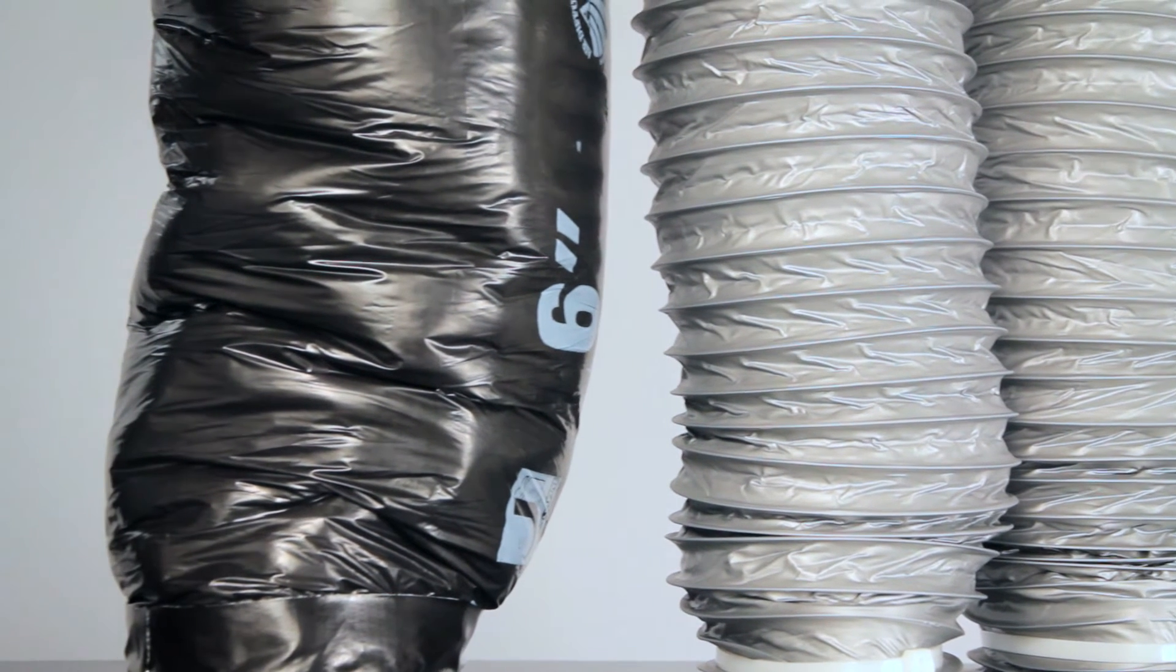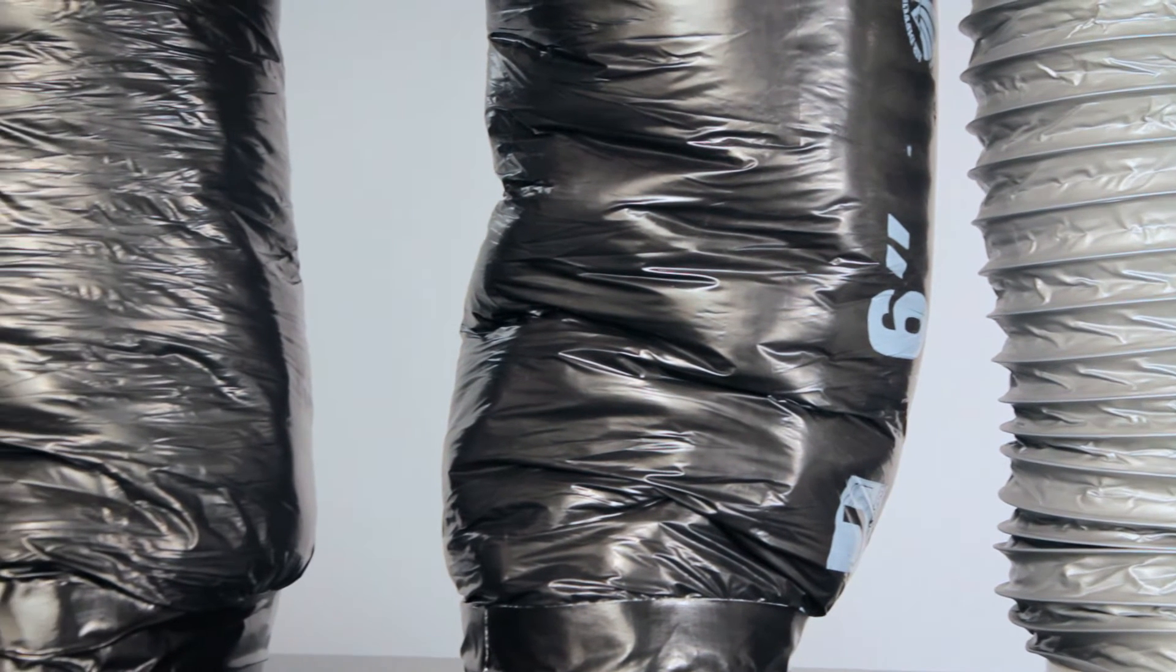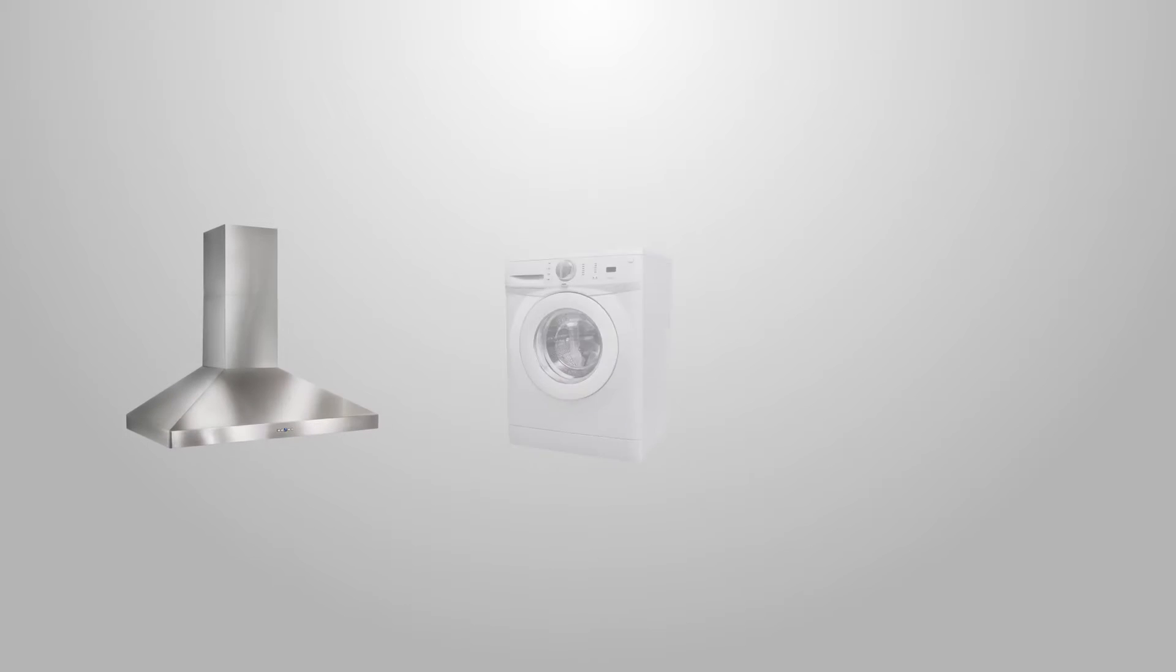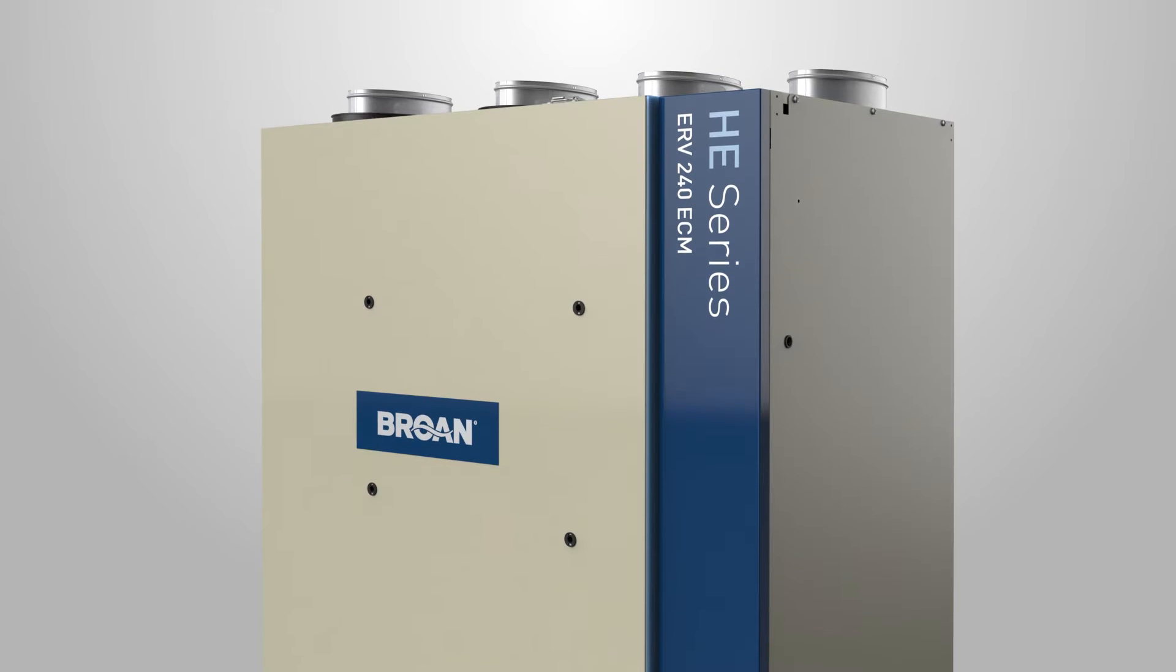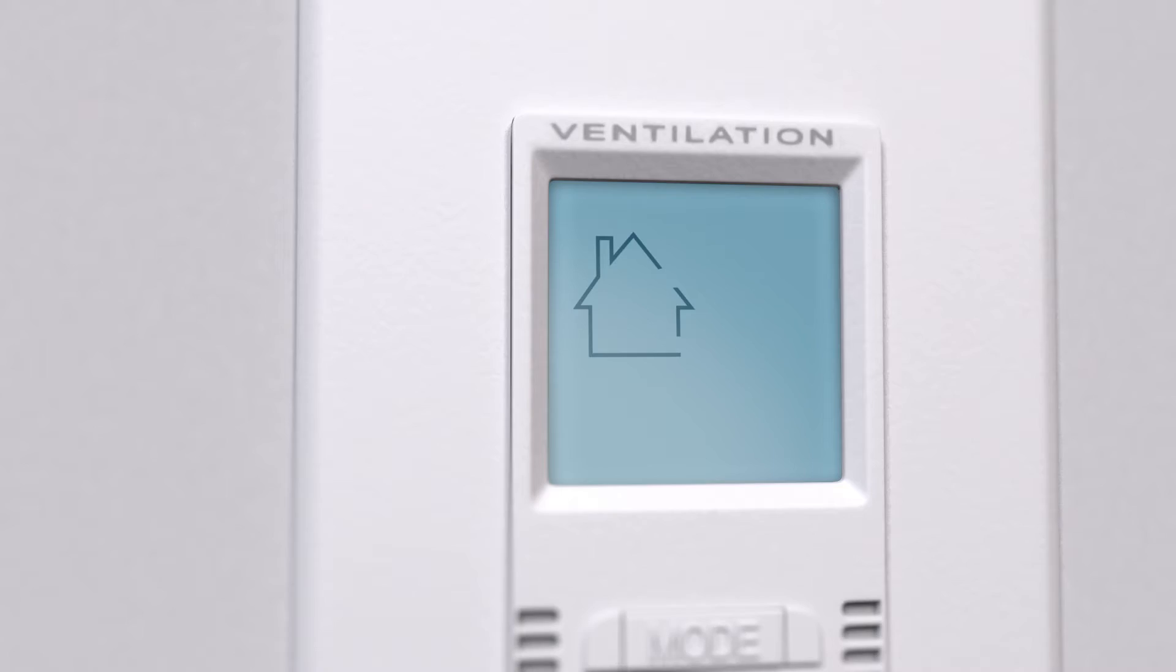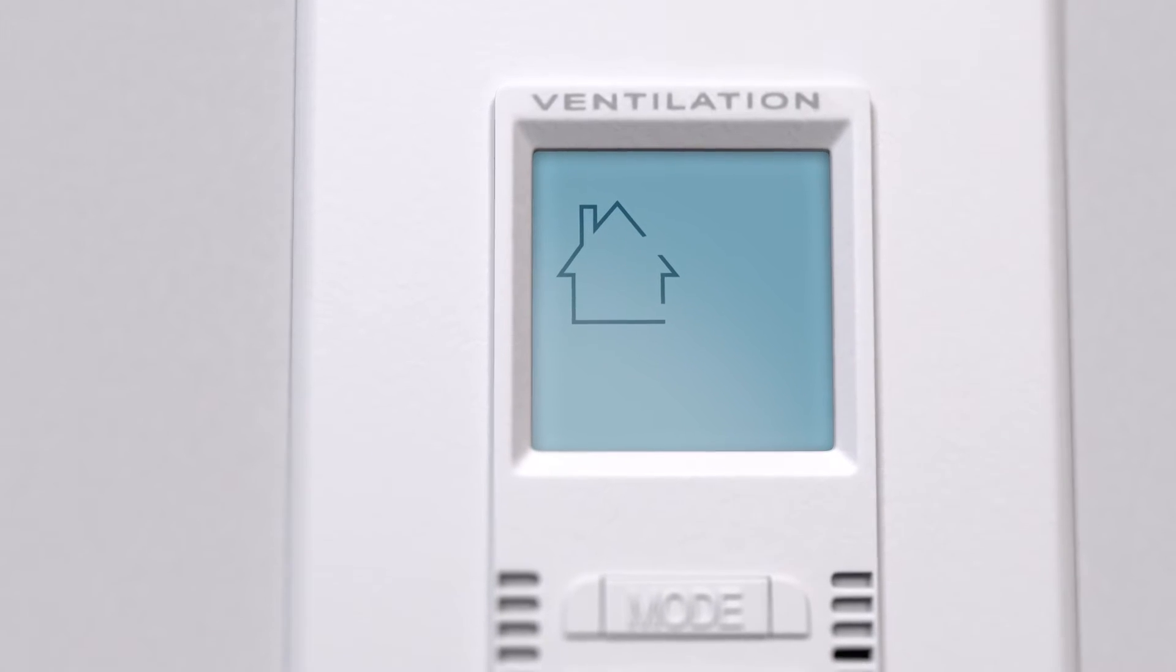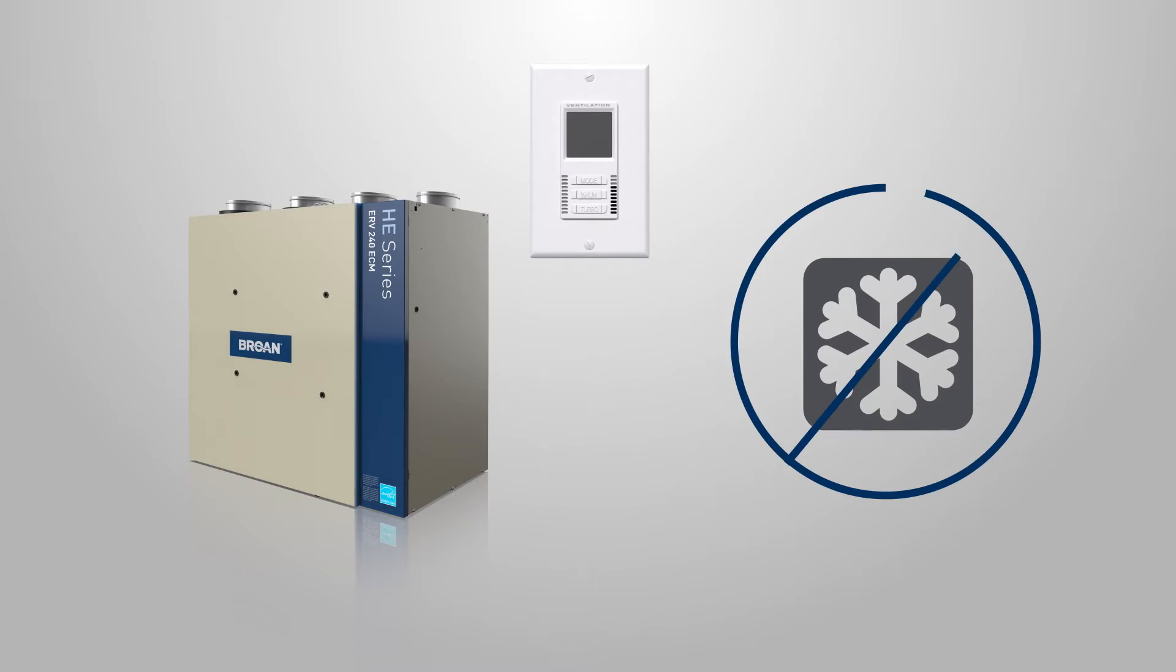Seal all the unit ductwork with tape and close all windows and doors. Turn off all exhaust devices such as range hood, dryer, and bathroom fans. The special design of these units, combined with the new wall control, now offers a great feature. No automatic defrost cycle will perform during the balancing steps.